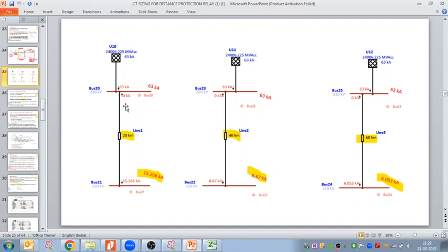So if my substation fault current is 63 kiloampere, and my transmission line protected length is 20 kilometers, then a fault after 20 kilometers is what we refer to as the through fault current. That value would be very low, only 15.26 kiloampere. When the line length increases, the through fault current value will decrease also. We did these simulations yesterday with the help of ETAP.